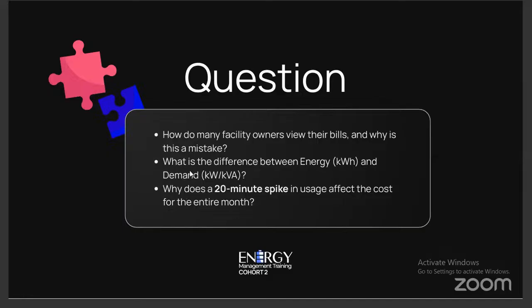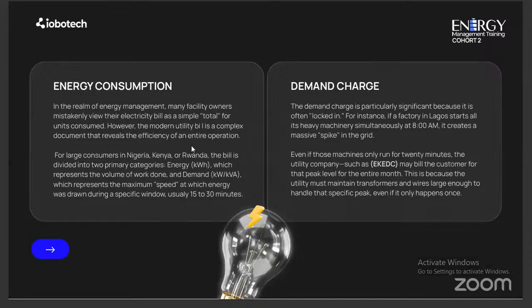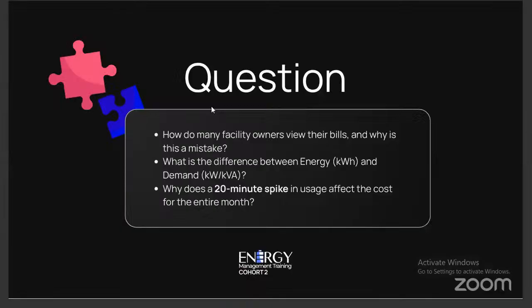So for the first question, it says how do many facility owners view their bills? I think they view it as just the total unit consumed by the facility over the period of time. That's how they view it. And how is it a mistake? It's a mistake because over time the total unit used does not really tell the full picture of what is there. You have to take a holistic view of how the energy is being supplied at each moment, because there are peak periods, and at every moment you must be able to make provision for the peak period. If you get to the peak period and there's not enough supply for that peak period, then there will be a failure in the system. So that peak demand must be supplied, whether you are in peak period or off-peak period. There must be provision for that peak period to be met at all times.